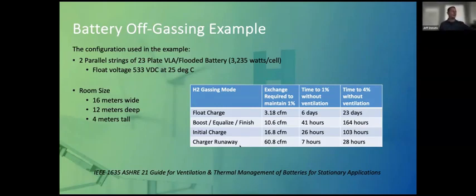Now, if you look at the gassing mode, you see that the IEEE 1635, as I mentioned before, breaks it down into best case and worst case scenarios. So best case would be that you have a float charge that's producing some hydrogen. You have a boost, equalize, or finishing charge. And what I mean by the boost and equalize, I'm kind of saying in the same light. Finishing charge is when a battery reaches 90% of charge and it's going into its final state of charge for the last 10%. So we consider that a finishing charge. Initial charge would be if I just installed the battery and I'm giving it an initial equalized charge. And then charger runaway means that the charger is malfunctioning and ramped up to its maximum voltage and basically causes the battery to go into thermal runaway.